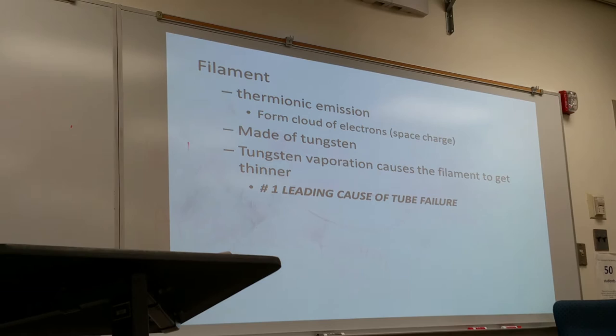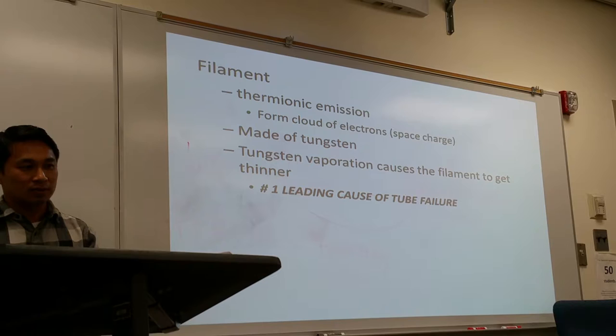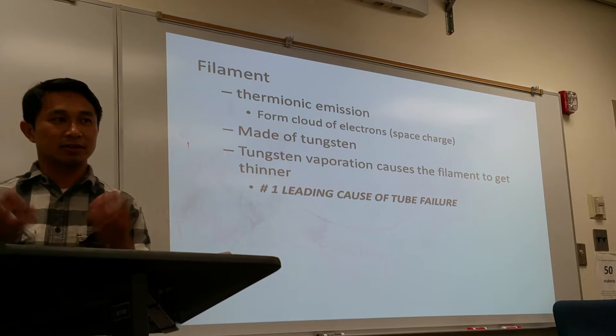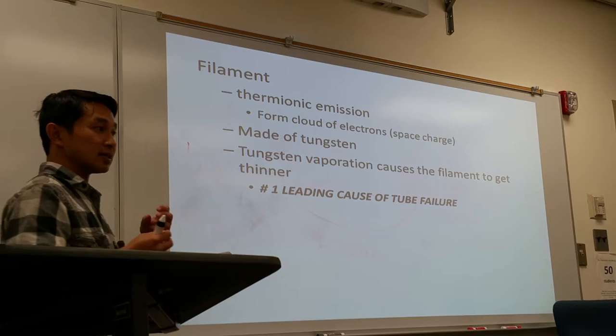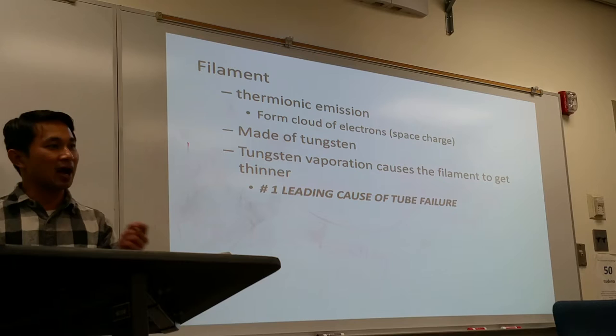The filament is where thermionic emission occurs. When current flows through the filament, it starts to glow very hot. It then produces what we call space charge, which is just a cloud of electrons. As the space charge continues to build, these electrons will escape from the filament. The escaped electrons become the projectile electrons, traveling from the filament straight to the anode side at very high speed.